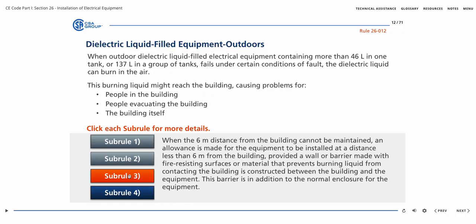Sub-Rule 3 provides that when the 6-meter distance from the building cannot be maintained, an allowance is made for the equipment to be installed at a distance less than 6 meters from the building, provided a wall or barrier made with fire-resistant surfaces or material that prevents burning liquid from contacting the building is constructed between the building and the equipment. This barrier is in addition to the normal enclosure for the equipment.